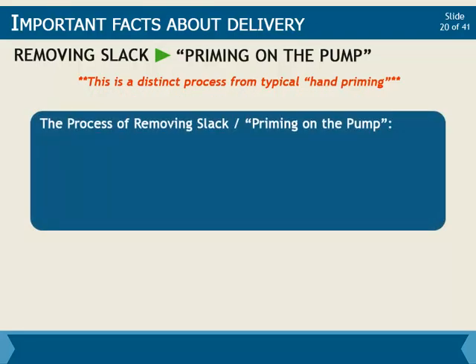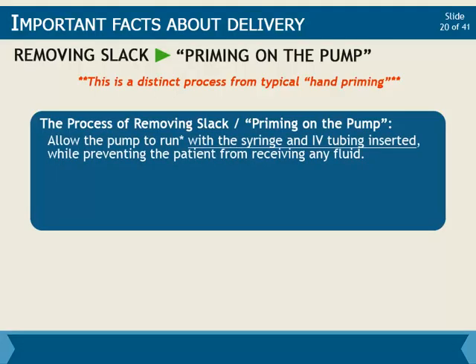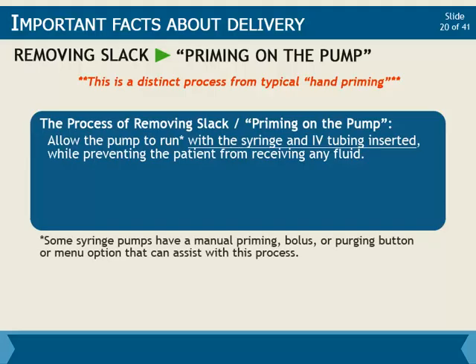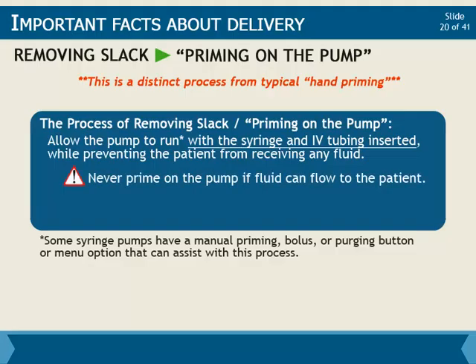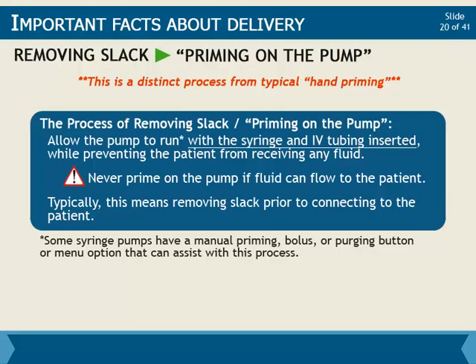Performing the process of removing slack will be different depending on the model of pump you are using, but the essential process is to allow the pump to run with the syringe and IV tubing inserted while preventing the patient from receiving any fluid. Some syringe pumps have a manual priming, bolus or purging button, or menu option that can assist with this process. However, you should never prime on the pump if fluid can flow to the patient. Typically, this means removing slack prior to connecting to the patient. If fluid flow were permitted to the patient, this process of priming on the pump would deliver an inadvertently large bolus.